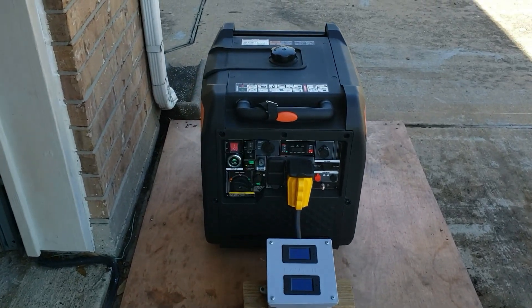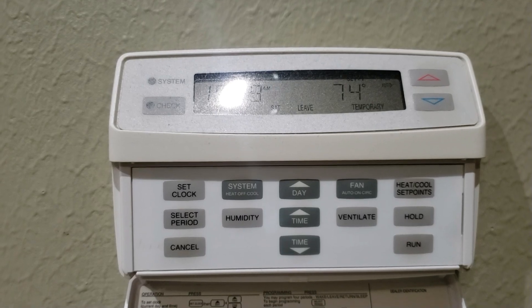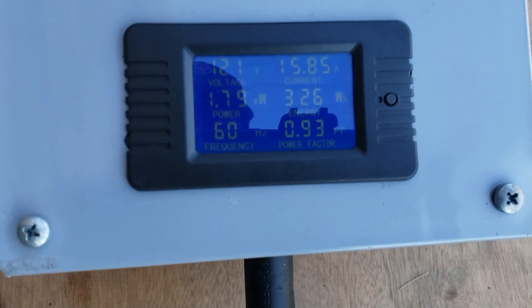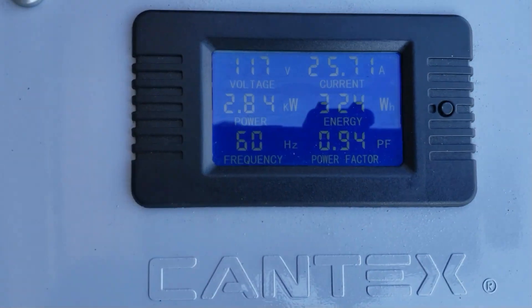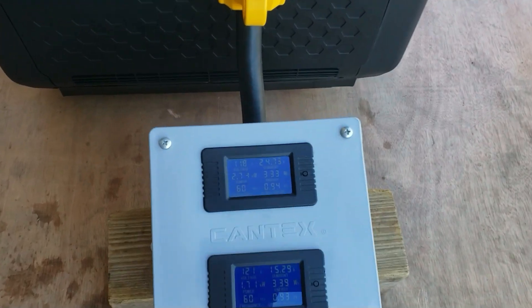I'll get inside and turn on some ceiling fans, then we'll hit that 5-ton AC. I'll come back out before it starts so we can see the surge — let's see if this thing can start a 5-ton AC. I'm at the AC, I'm going to lower the temperature to make it kick on, then try to get outside before it starts. We're pulling 1.8 kilowatts on this leg and 2.8 kilowatts on this leg. We're at 100% — the 5-ton AC is running. I barely made it out here but it started with absolutely no problem.